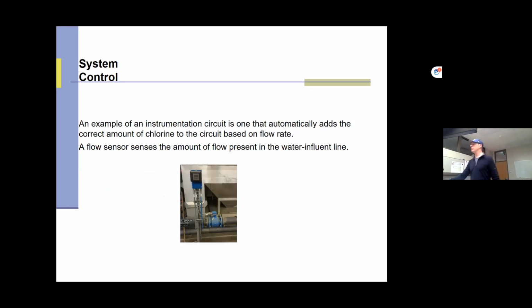Here's a pretty good example of an instrumentation circuit. It's pretty small, but it shows here, this is a flow meter. And basically you can see it's sending a signal from that flow meter in that pipe to a controller. And that little controller is sending a signal to a chlorine analyzer that's saying, hey, if there's not enough chlorine, I need to put more chlorine in. And that's all it's doing. It's taking a look at that. As flow increases, then that number of the flow is going to change how much chlorine you got to put in. And that's all done through a programmable logic.